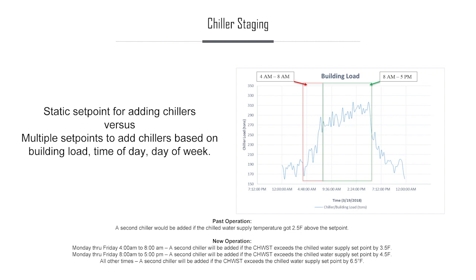It says, yeah, you know what, in the morning, we actually need to get the building up to temperature real quick, so we're going to go with the 3.5 degree before bringing the chiller up. Now, if you have to add another chiller, we're actually going to bring this to a 4.5 degree, just to stretch out the time limit, because more often than not, by the time that extra chiller was needed, people were actually heading out the door. And we could just kind of coast the building, let everybody leave, the labs are shutting down, and then let the evening time with the existing chiller recover everything for the next day.